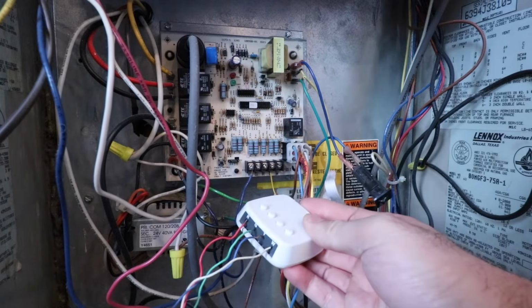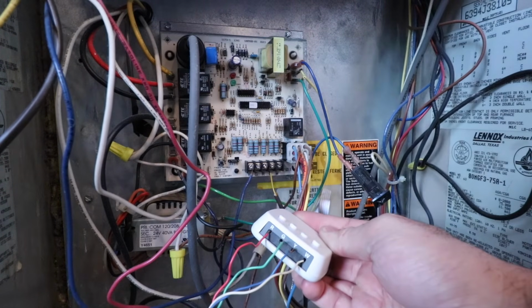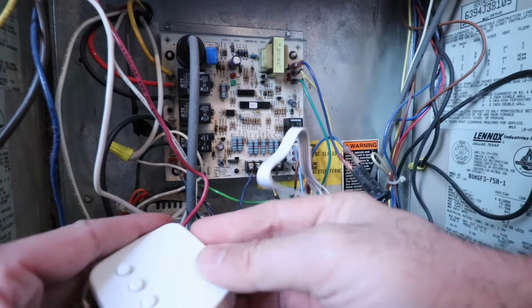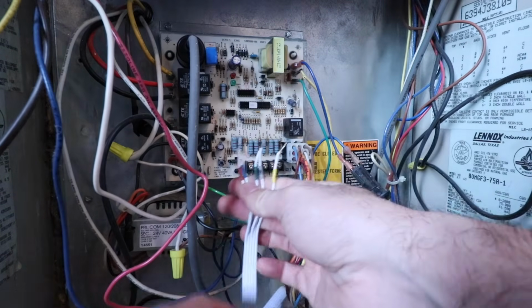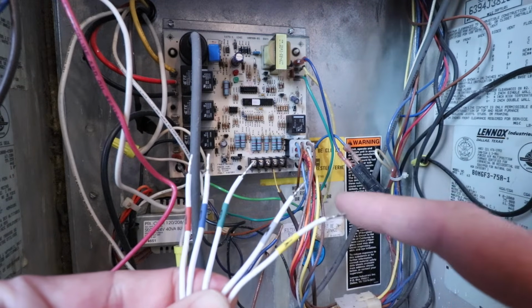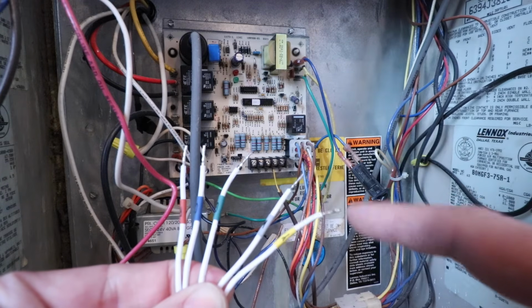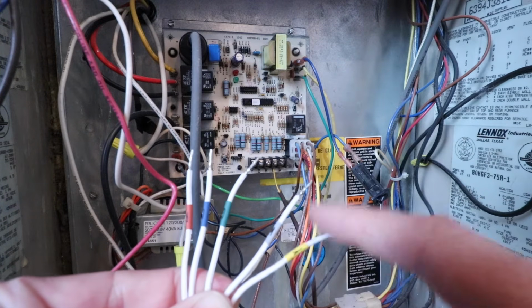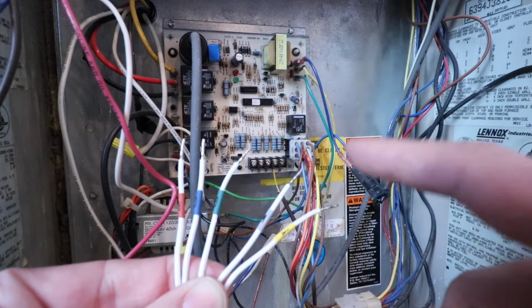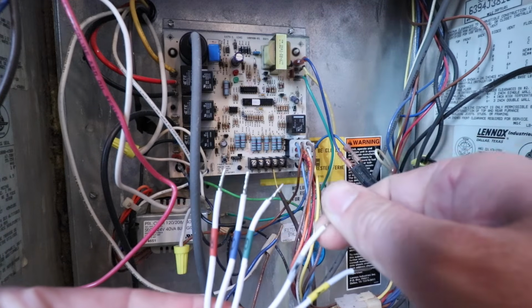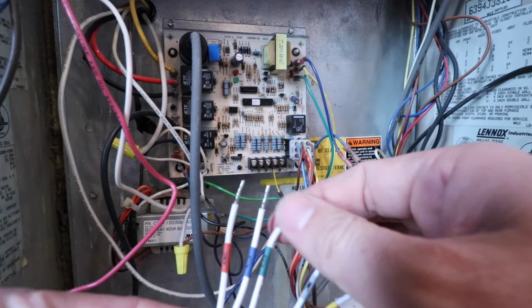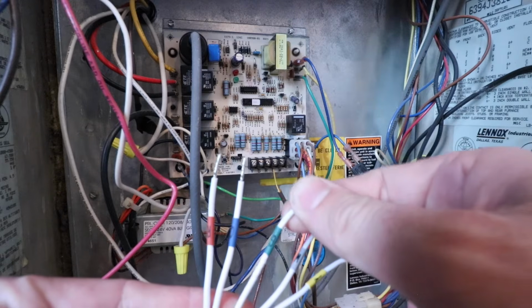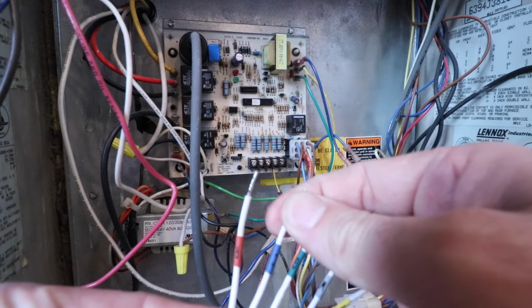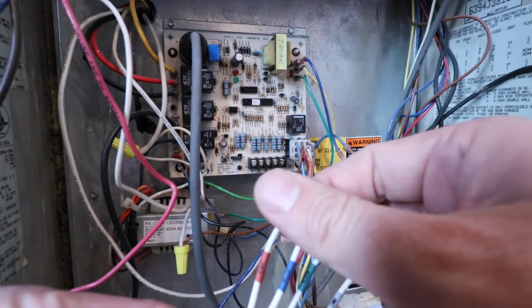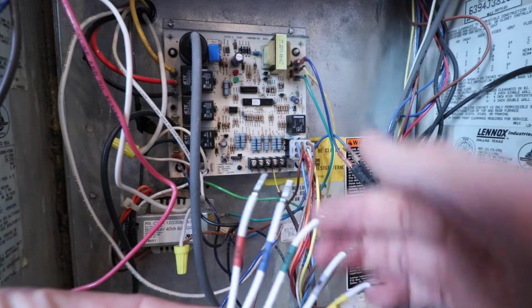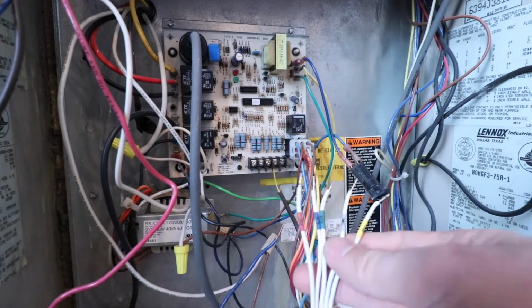Now we've got all those wires connected in the power extender kit, and we're going to wire it up to the proper terminals. Each wire on the kit is labeled: the Y terminal goes on the Y terminal on the circuit board, the W wire goes on the W terminal, the G wire on the G terminal, the C wire on the C terminal, and the R wire on the R terminal. So we'll go ahead and wire that up.